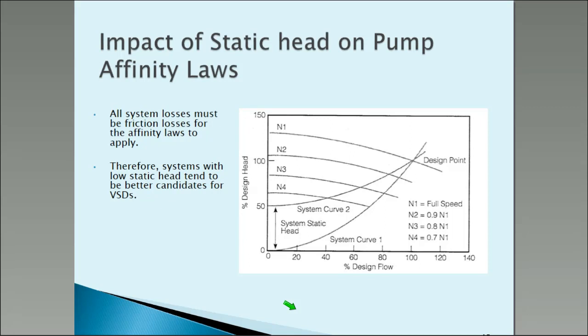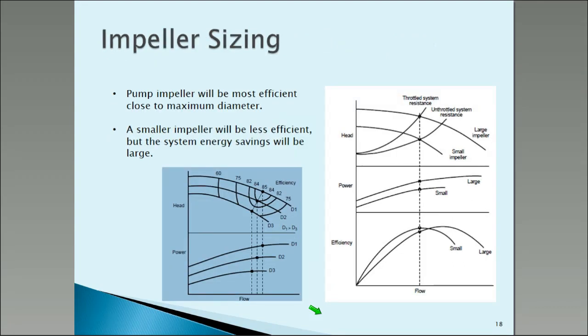This is a really important curve that distinguishes again between static head and friction head. If we've got an all-friction system, we can produce operating points down to as low a speed as we like — N1, N2, N3, N4, N5, N6 — and we still have an operating point. But if we're in a system with significant static head and we go down to N5 — reduce it even further — we have a problem. The pump may be producing less pressure than the system needs. We then have a non-pumping situation — it won't work. So if you've got any considerable static head, think very carefully about using a variable speed drive because it may not work. You do see such systems in the industry where variable speed drives have been sold and installed in the wrong application.